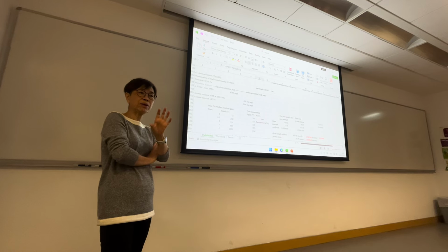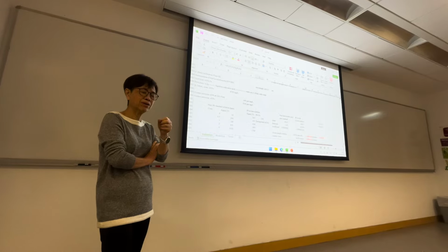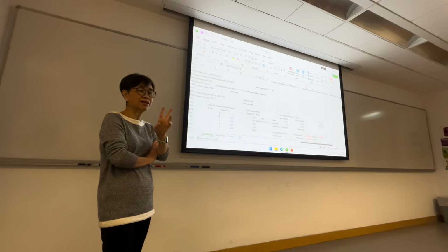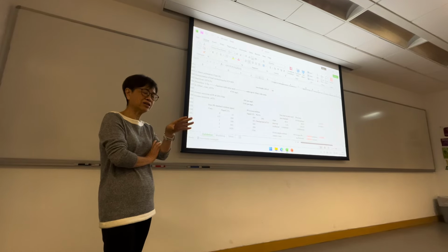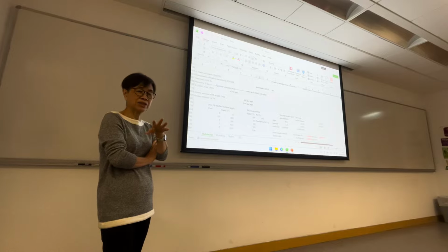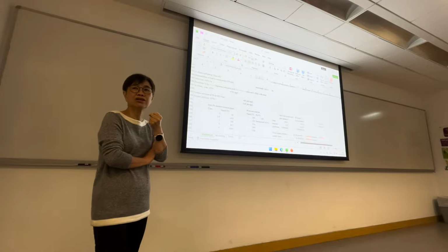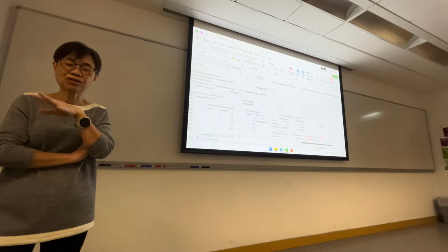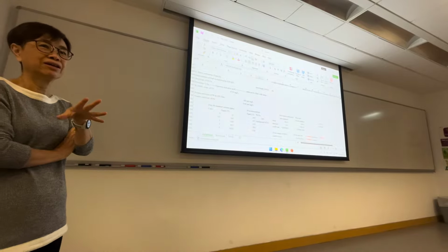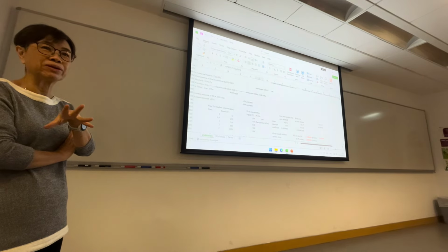So it all depends on your instrument. If the instrument is good enough and your pipeline, your pump is large enough, then it will not have any difference, okay? The total mass entering the ICP-OES will be the same. But if the pipeline is quite narrow, it will be affected by the viscosity. So I can't say that you must match the calibration blend with the solvent blend. It all depends on the instrument. You need to check.